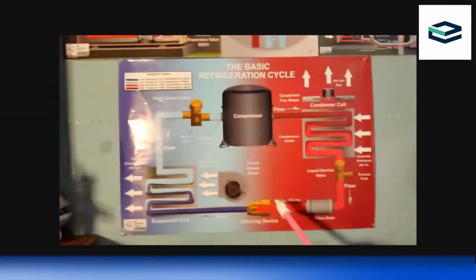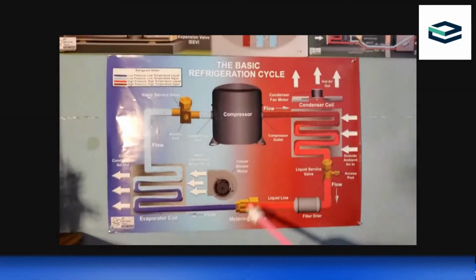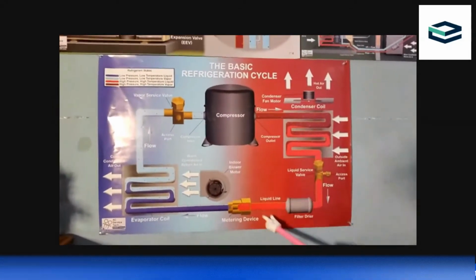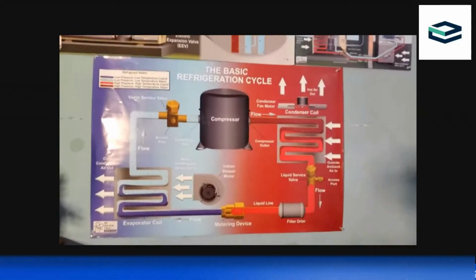We're going to change our TXV or our piston metering device or whatever we're changing, the filter dryer. Sometimes there is a filter dryer in this. We will talk about what those do in a second. But we're going to change whatever we're changing, and then we're going to make sure we have a tight system again. So a tight system, I don't mean that I did a really good job, and so I'm saying it's a tight system. I mean that I have finished my work.